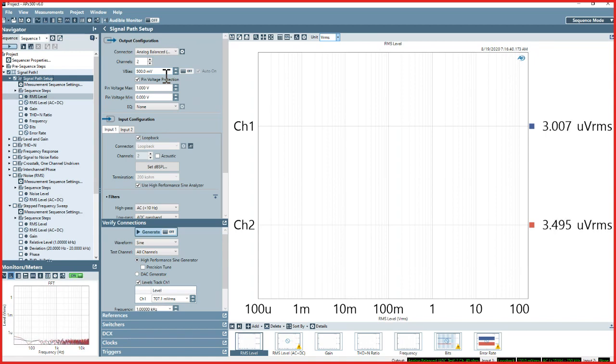Hey, Dan, I've got a question for you. Yes. The question is, what is the analog output transit time when it changes range, assuming that I set it to auto? So if you set it to auto, the range change time is in the period of milliseconds.